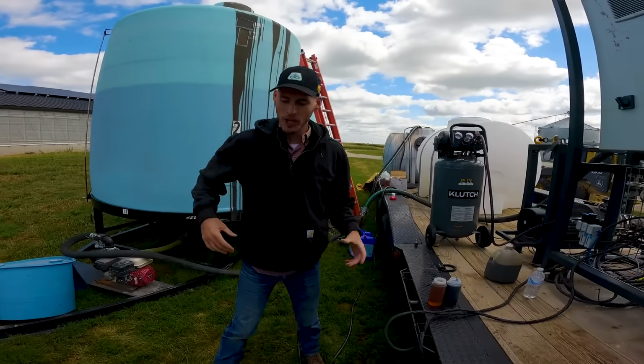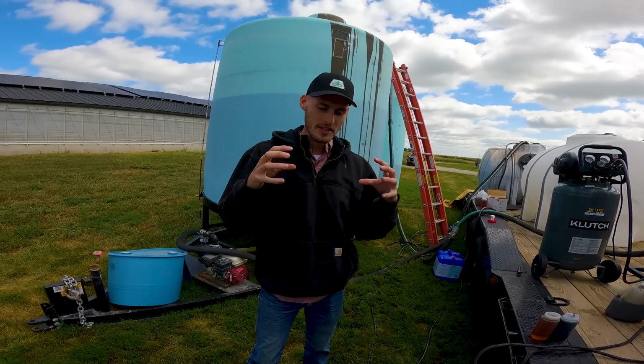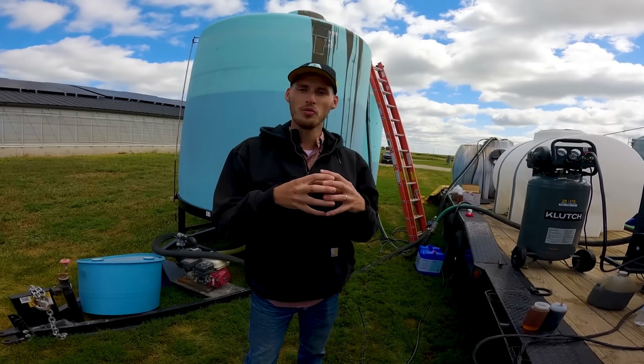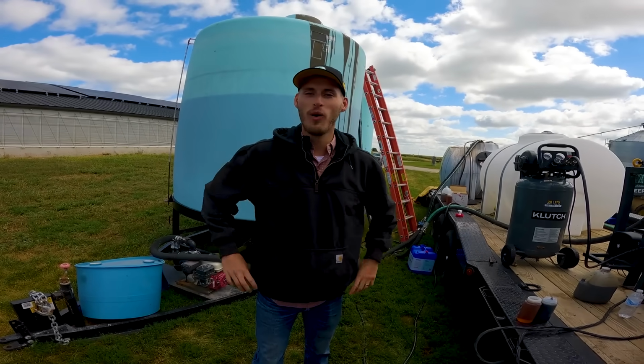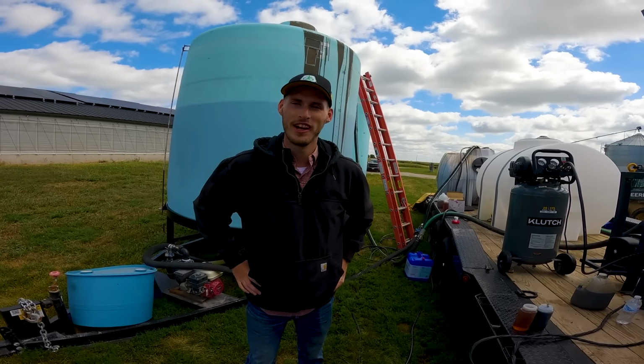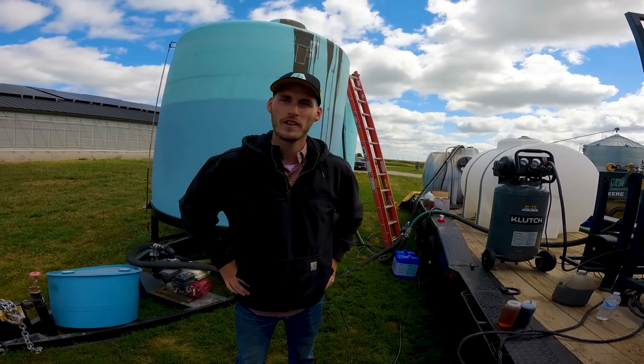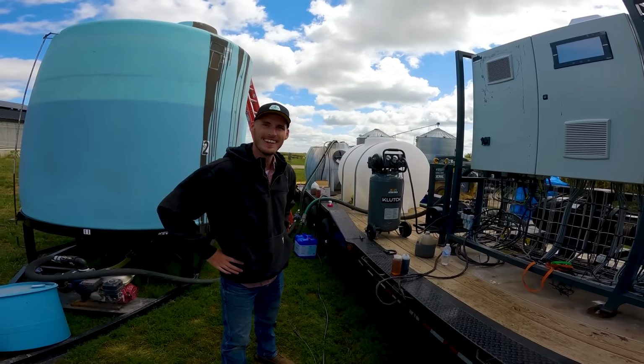Yeah, so once it gets to this brine, we'll concentrate it and run it through an RO, and that RO will allow you to get your brine to the nutrient value you want, and it'll reject water that can be reused and recycled. And the water will be clean, right? Correct. So you could feed it back to the pigs or just discharge it if you wanted.